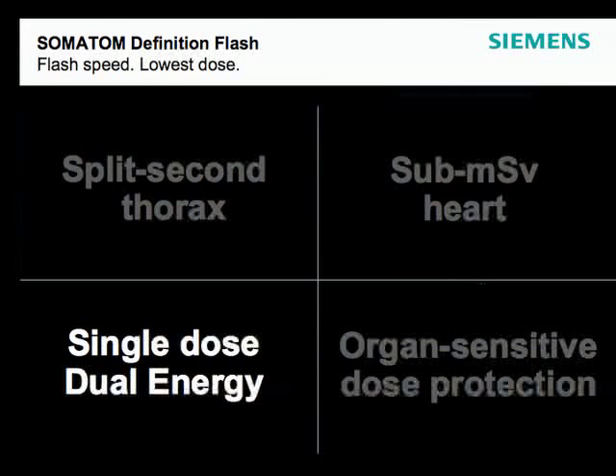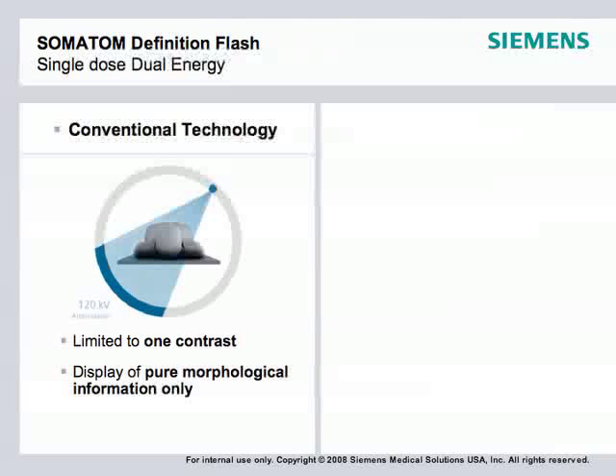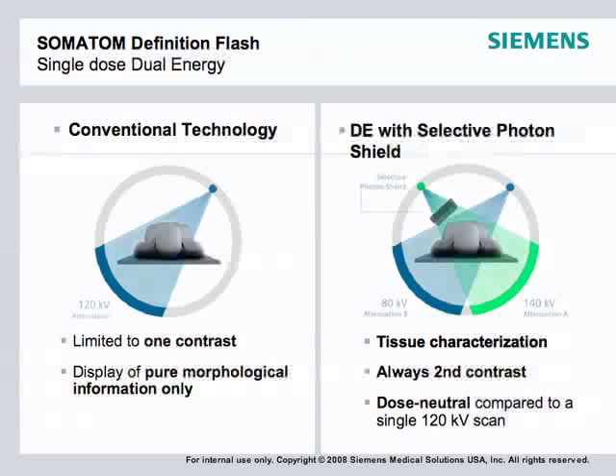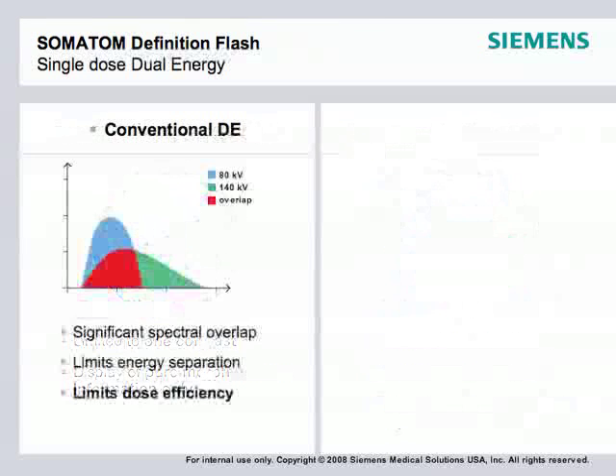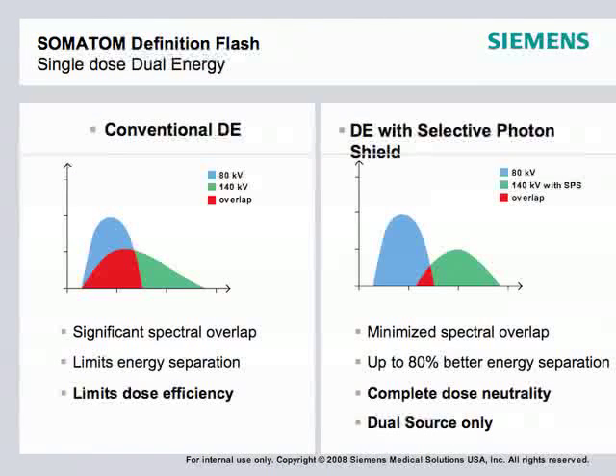Dual energy can now be done in a dose-neutral environment, using tissue characterization with two tubes at 80 kV versus 140 kV. The selective photon shield brings dose levels down to neutral by filtering out low energy coming off the high 140 kV source. This moves from conventional dual energy with significant spectral overlap to minimized spectral overlap — 80% better spectral separation — enabling new software developments and dual energy applications.